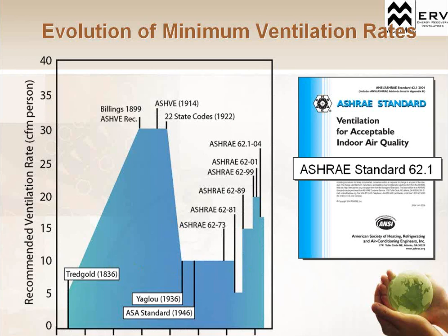And it was right around 10 CFMs for quite a while until we get into about the 80s, the late 70s, early 80s, when we did a couple of studies on actual ventilation in a building and how inefficient ventilation is. Because we're bringing in outside air that now I have to pay to heat and cool, they actually reduced the ventilation standard to 5 CFMs per person.